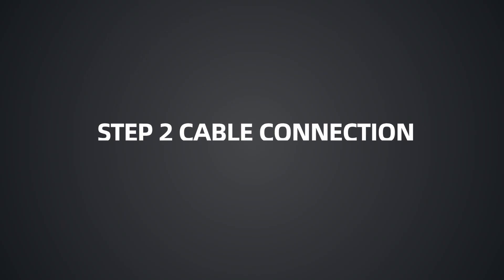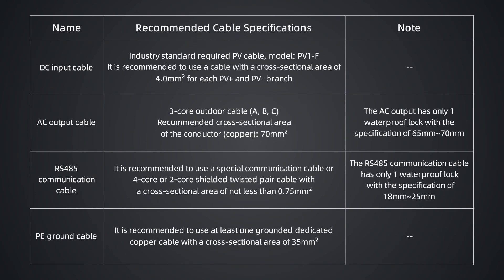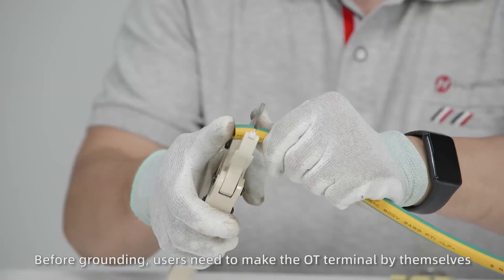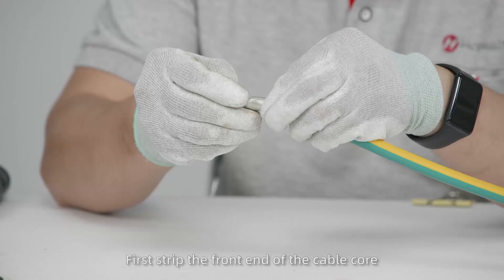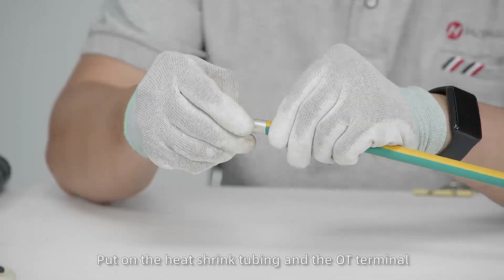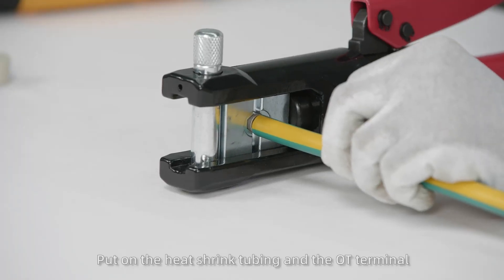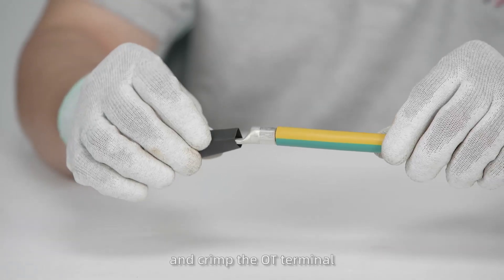Step 2: Cable Connection. First, connect the ground cable. Before grounding, users need to make the OT terminal by themselves. First strip the front end of the cable core. Put on the heat shrink tubing and the OT terminal, and crimp the OT terminal.